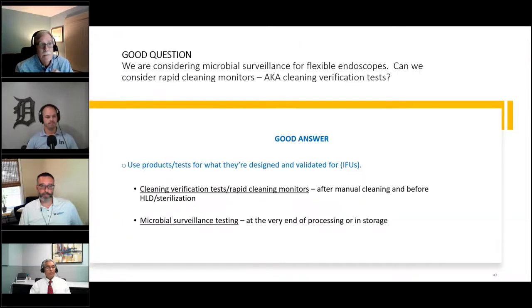So we have to use products or tests for what they're designed and validated for. Cleaning verification tests, also known as rapid cleaning monitors, are to be used following cleaning and before disinfection or sterilization. It's part of focused inspection after manual cleaning. Cleaning verification, as the name implies, tests for cleaning efficacy, indicating the presence of residual organic soil, such that if positive, this allows for re-cleaning and retesting of the device prior to disinfection.